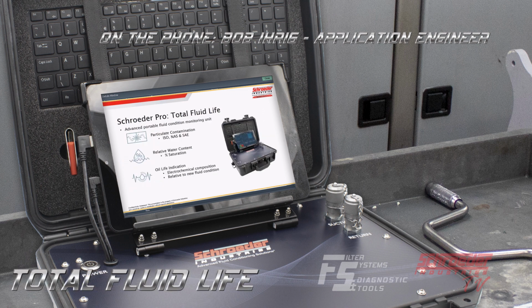So with that, I'd like to introduce the Schroeder Pro Total Fluid Life unit first. And with this unit, we can measure particles according to different standards. The main standards, ISO, NAS, SAE, which many of the current portable fluid condition monitoring units already do. Relative water content as a percentage saturation, temperature, not really all that differentiating. But what is differentiating about this product is the ability to estimate oil life.